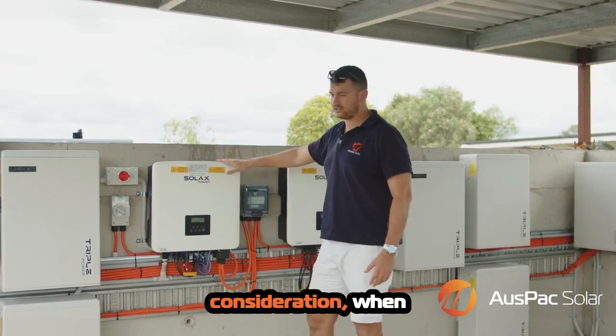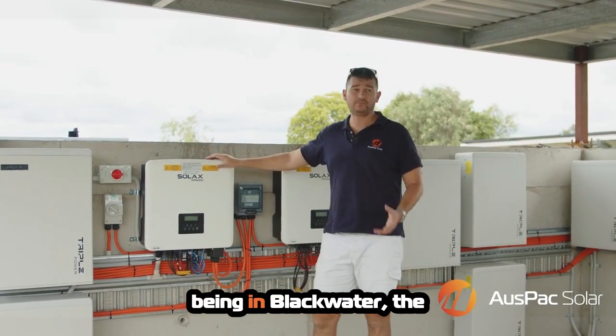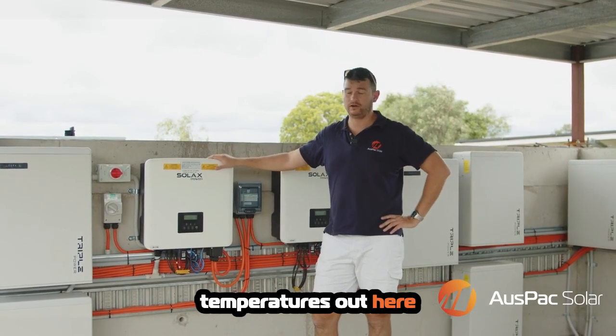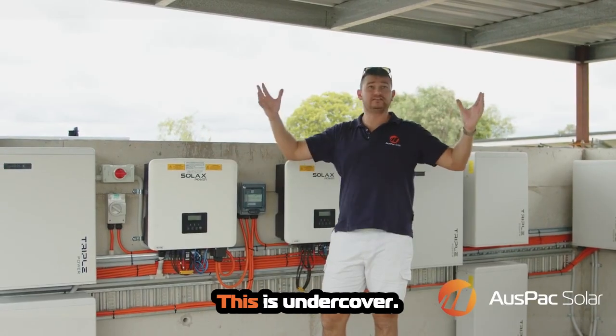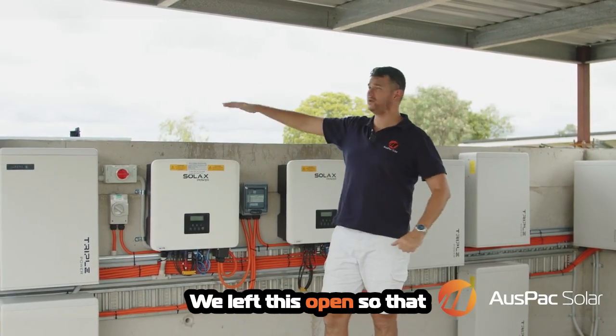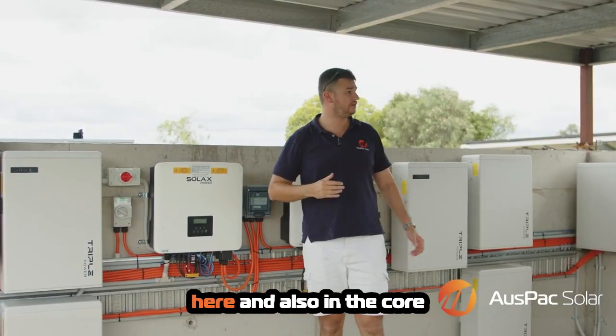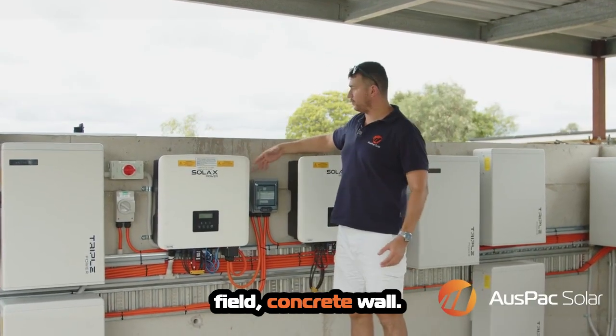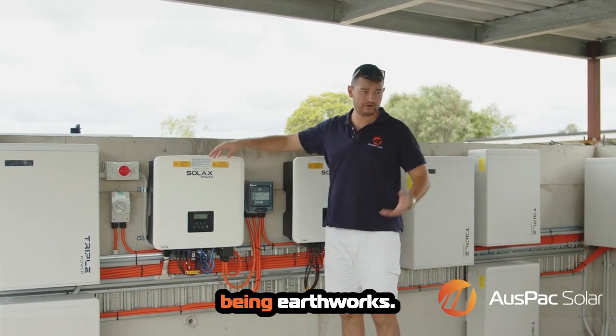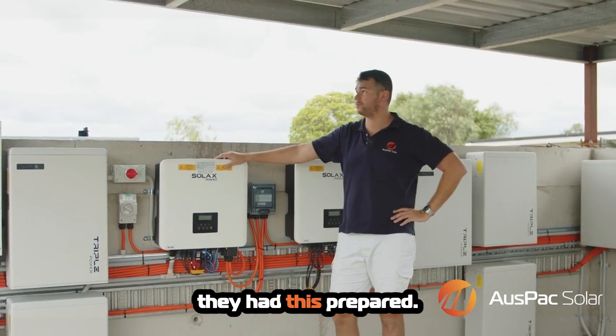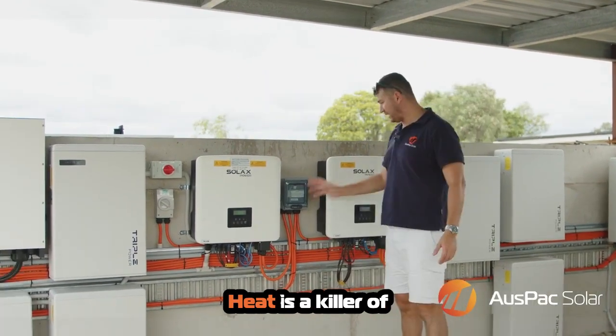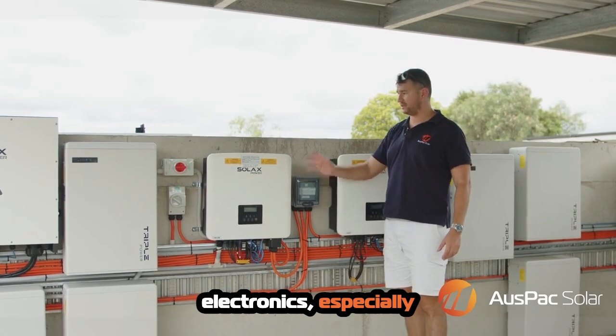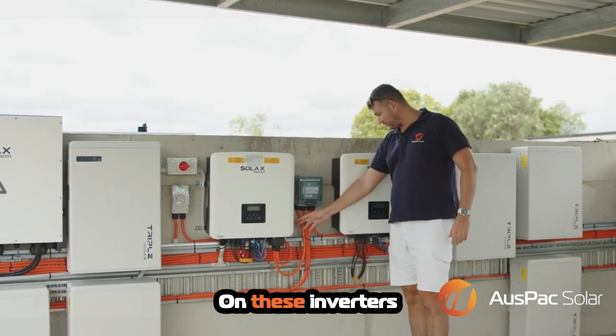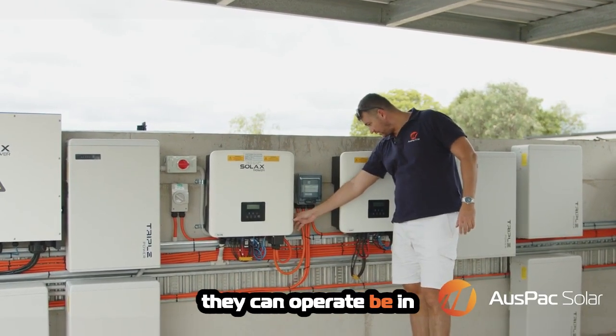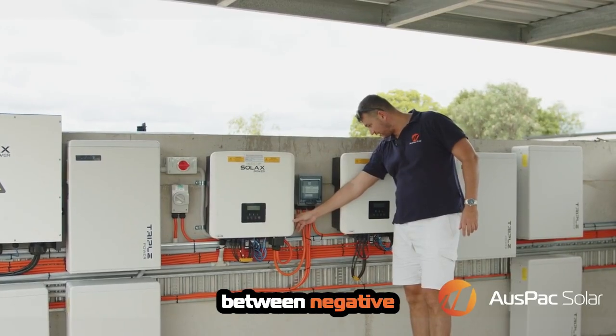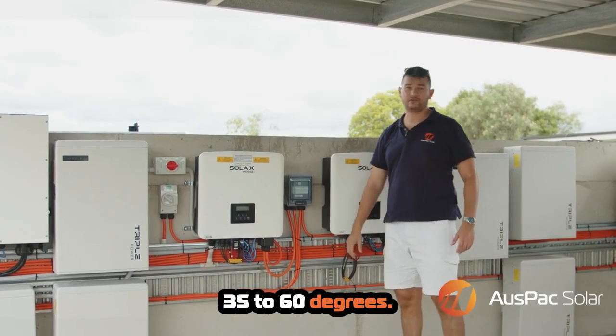Now the other consideration when we're doing the installation design, being in Blackwater, the temperatures out here are like 45, 50 degrees. This is undercover. We left this open so that we could get air through here, and also the core filled concrete wall. This was all done by the customer. Being Earthworks, they concreted it and they had this prepared. They also had a booster. Heat is a killer of electronics, especially batteries and inverters. On these inverters, they can operate in a temperature range between -35 to 60 degrees.